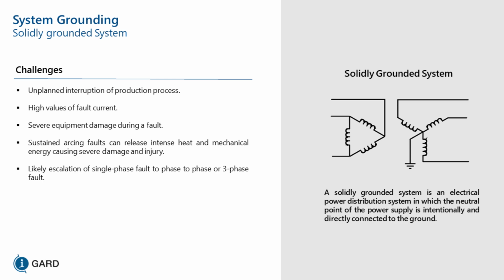And the codes, both the NEC and the CEC, say that if you have a solidly grounded system and your voltage is higher than 150 volts to ground, and greater than 1,000 amps, you must have ground fault protection. You have severe equipment damage where the fault occurs. Sustained arcing can release mechanical energy, causing severe damage and injury, likely escalating a single-phase fault to a 3-phase fault.